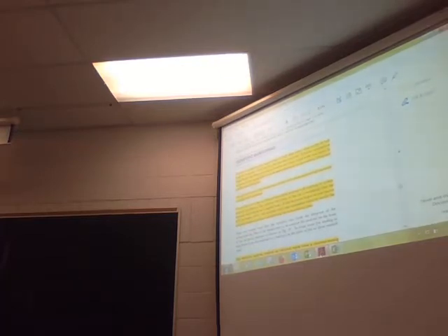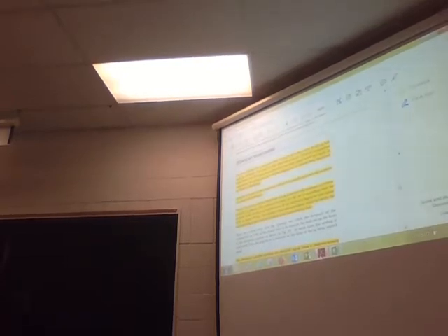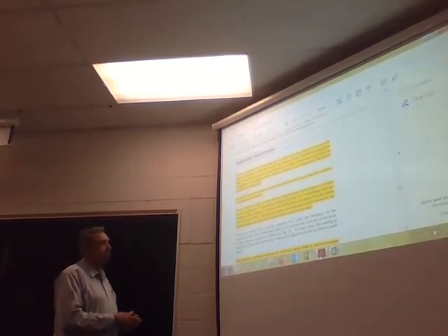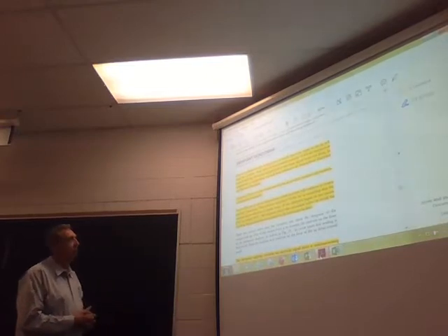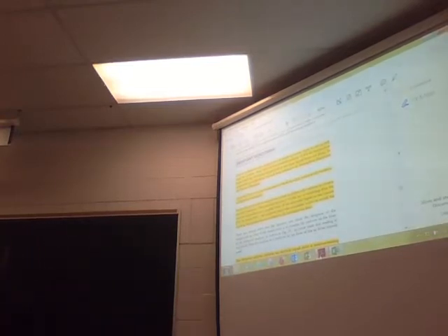Pressure dew point of air is something that the operator must check on a regular basis. If the dew point begins to rise, from minus 60 toward minus 40, the operator must take immediate action to rectify the situation before moisture accumulates in the instrument air. So if it starts to rise, you've got to figure, hey, we better regenerate this, or change this.